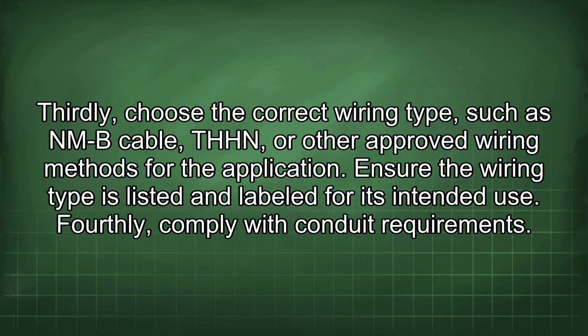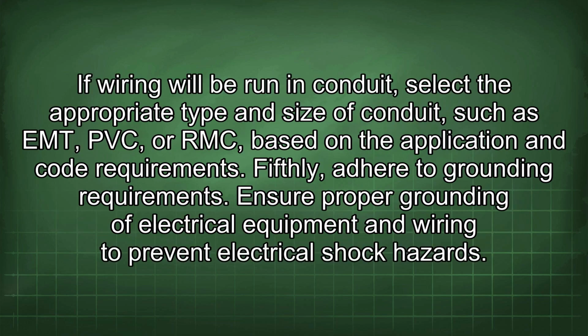Thirdly, choose the correct wiring type, such as NMB cable, THHN, or other approved wiring methods for the application. Ensure the wiring type is listed and labeled for its intended use. Fourthly, comply with conduit requirements. If wiring will be run in conduit, select the appropriate type and size of conduit, such as EMT, PVC, or RMC, based on the application and code requirements.